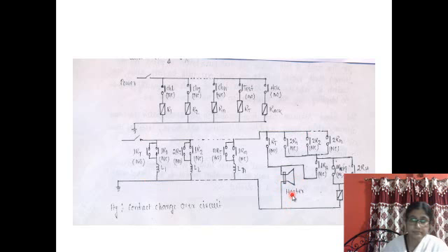And next step is acknowledgement. This is the fault detection, and then it should be acknowledged, because a certain time will be required to remove the error or to correct the error that occurs in a particular control loop. But during this period, the Hooter must be turned off, otherwise a huge noise will be produced in the plant.